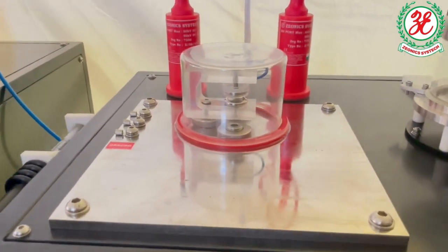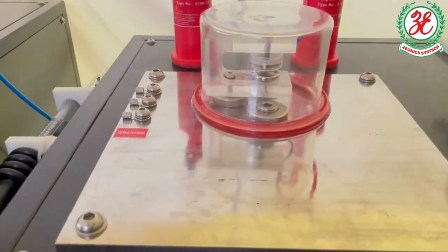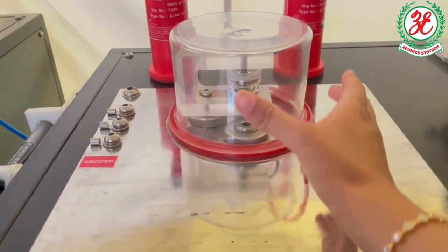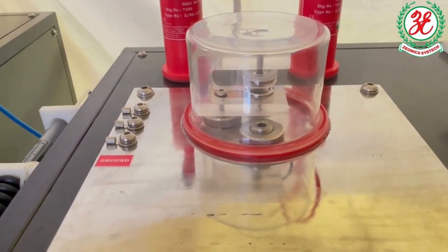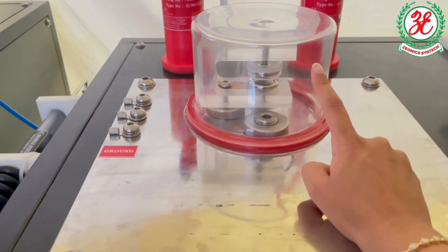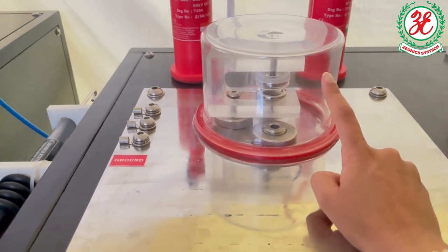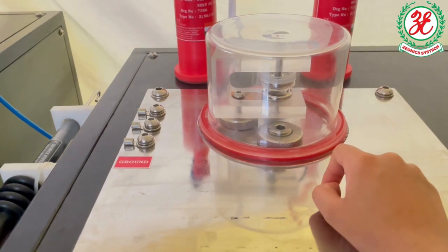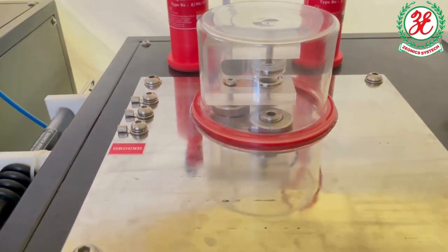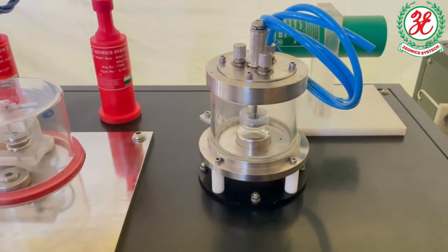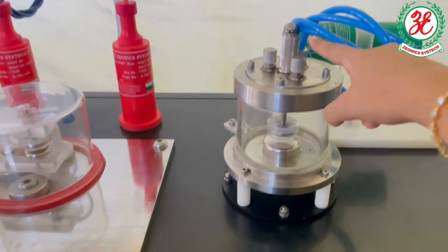To discharge the voltage, you will release the vacuum of the chamber, lift the glass top off, use the discharge stick to touch the top electrode, which is the high voltage electrode. Hold it for a few seconds till the discharge is complete, and then you may let go. For the external chamber, you may touch it to the top.